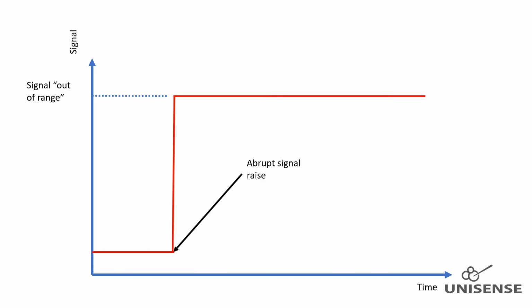A broken sensor will in water give a very high signal, typically out of range, as the working electrode is now directly exposed. So if the tip breaks during measurements, a sharp signal rise will occur to the out of range level. It is not possible to repair a broken sensor.